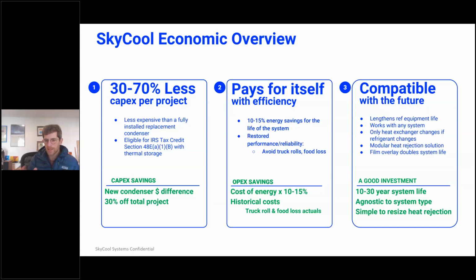But this would be tanks of water that the panels would cool at night, and then that would be deployed during the day. This is a somewhat new concept that the IRS essentially released language on within the last 2 months, but it's under the Section 48E ITC tax credit. The system also saves energy, so it's reducing energy use for the cooling system, and so it's less capex. It saves energy. You're going to avoid issues with the refrigeration system in really hot times, avoiding, for example, refrigeration contractors having to come to a site. You're avoiding food loss if the rack shuts down as well.